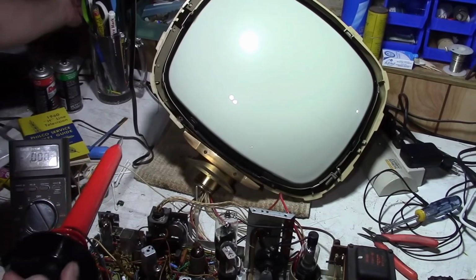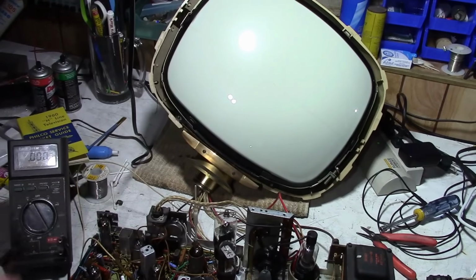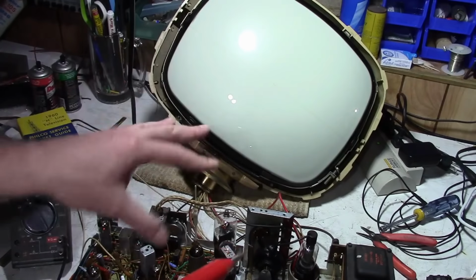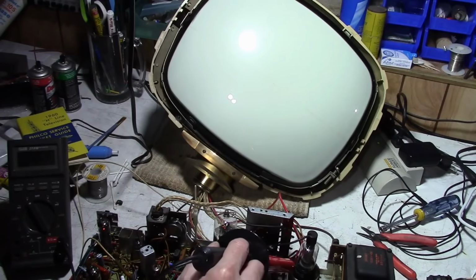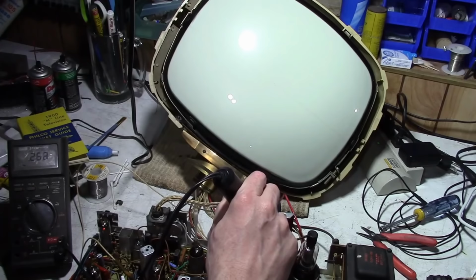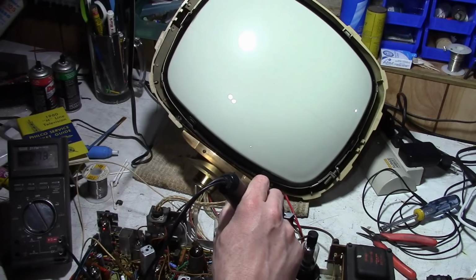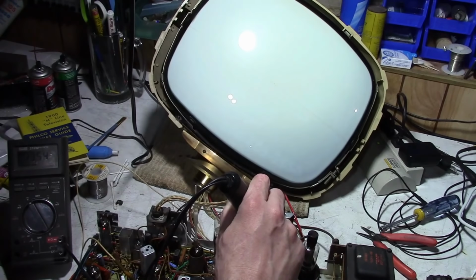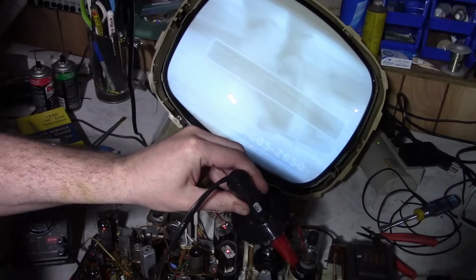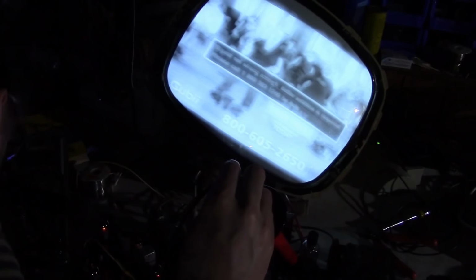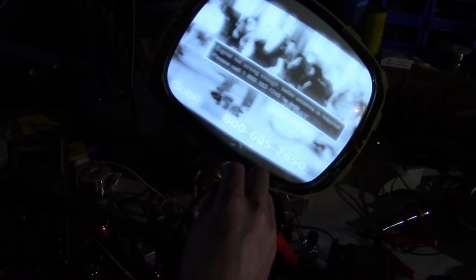Alright, another power up test. With the high voltage cage out of the way, I get the high voltage probe right down in there on the anode. And we got 13,500 volts, almost 14. And the picture is super crazy out of focus.